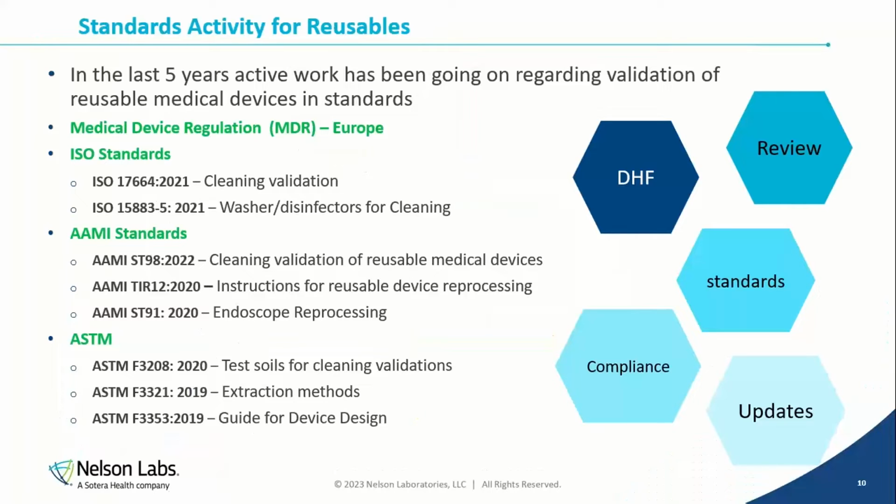Now, just to give you an overview of what standards activity there is for reusable devices and what you should consider that your design history file should have for reusable is the MDR, right? You should have that in your design history file for reusable, the applicable parts of the MDR. The standards that were updated in the last 5 years, right, with the ISO standards, AAMI standards, and ASTM standards.